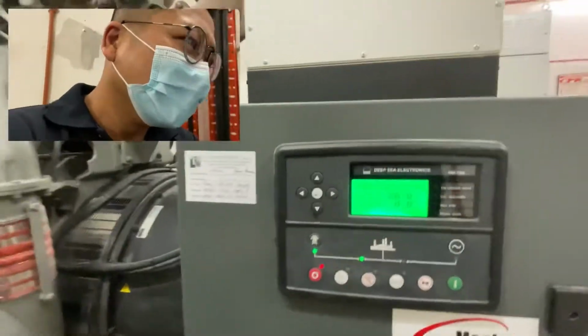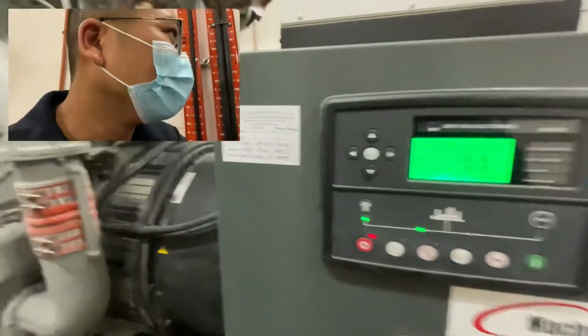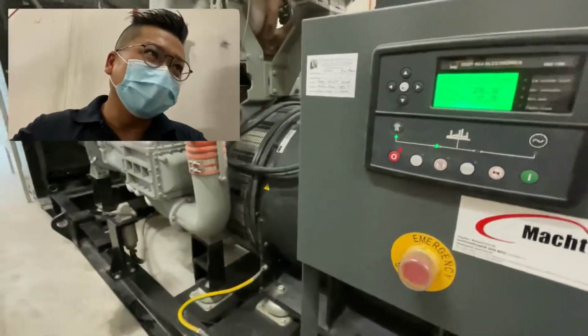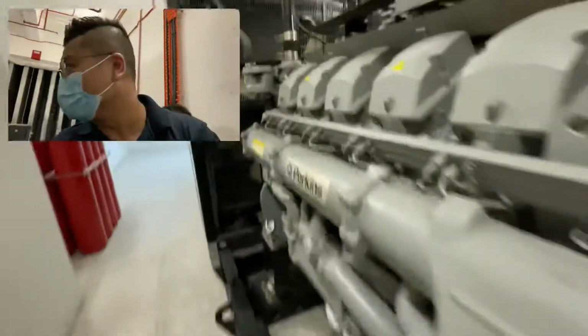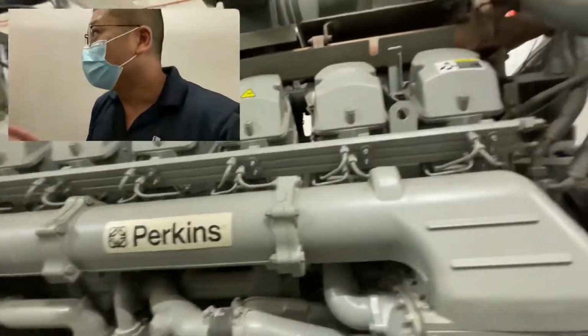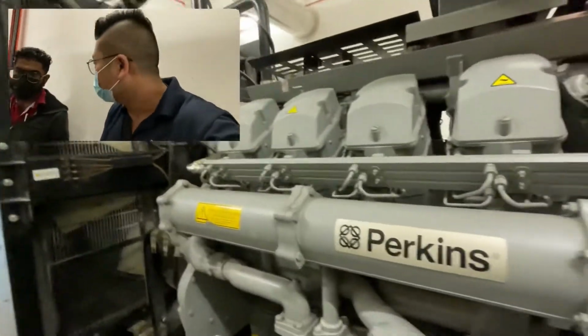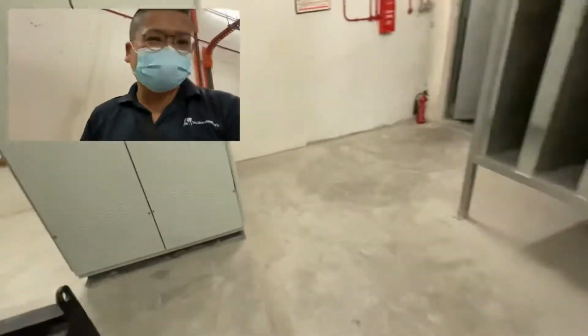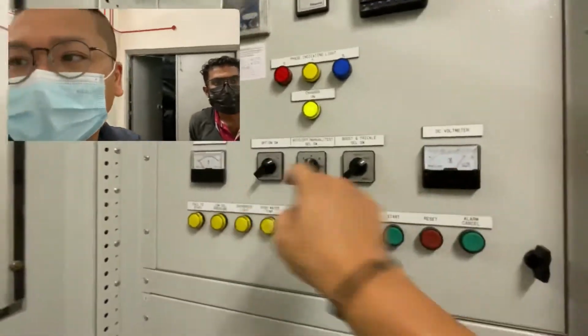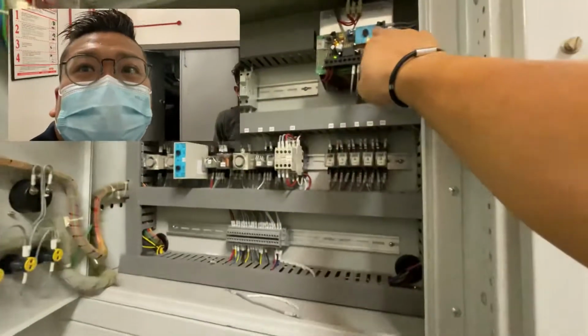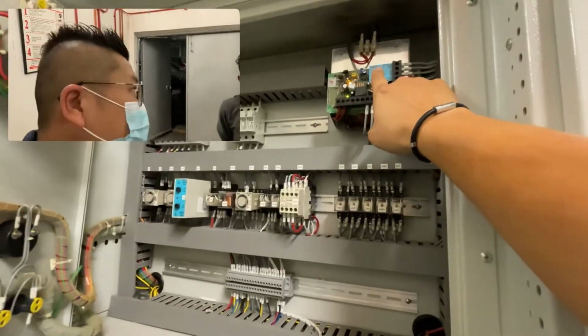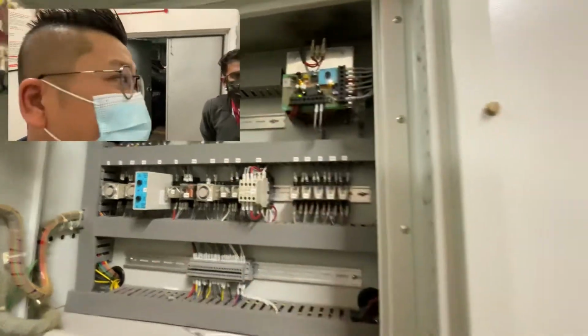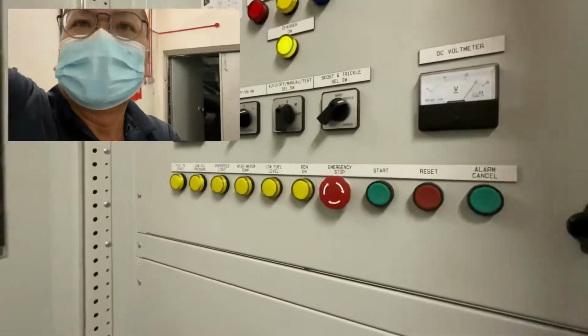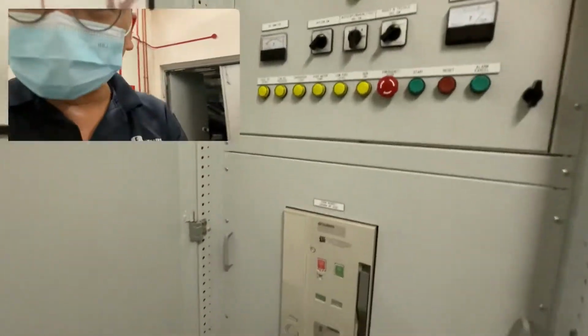Okay. Because all these starter, relay or everything is rated at 24 volt DC. If you go higher than that, the thing can be spoiled, or it will overspeed the genset during starting mode. So in between 27 and 28 is the best range before start of genset. So actually this voltage is acquired from the charger. This is the charger. Here, you can set the charging voltage by fine-tuning this adjustable rheostat, we call it variable resistor. Okay, so currently we are not going to test it, but we're going to have a routine check.